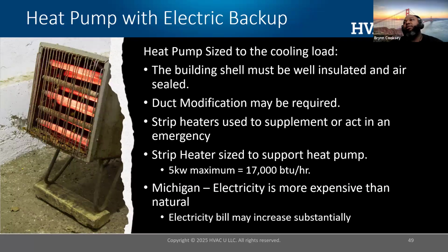Our second method was talking about sizing the heat pump to the cooling load and maybe using some type of electric backup. Also costly, and many times this is going to require duct modification because heat pumps require more airflow than a traditional furnace. As the heat pump capacity drops off if it gets really cold, the supplemental heat will come on and supplement the heat pump. The intent is for the heaters and the heat pump to run simultaneously. All right, we're going to use a heat strip or heater bank to supplement that. Again, when you put this type of system in, the customer's bills may increase substantially and they need to be warned about it.